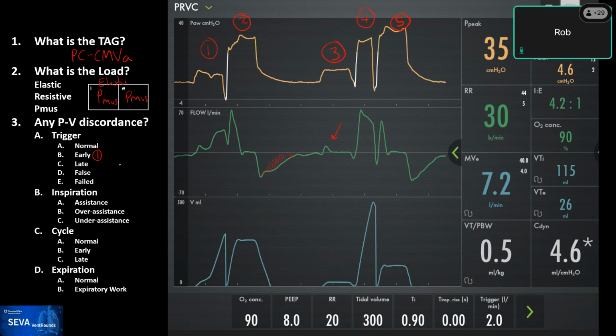Well, I sort of go with what you said for the beginning, because the breath is defined by the flow crossing zero positive and crossing zero going negative. So there's a breath there where you can see the two zero crossings in the flow. So that's one breath. And then immediately after it crosses zero, within a few milliseconds, the patient makes an inspiratory effort, and this is pressure triggered, a big enough inspiratory effort to pressure trigger two breaths. Thank you very much, Rob.